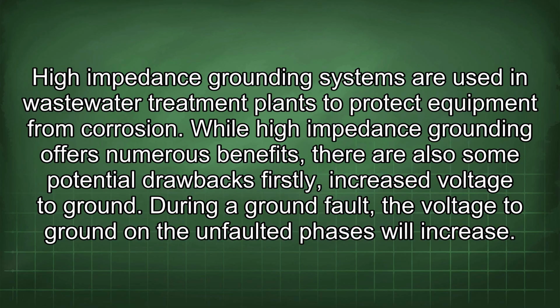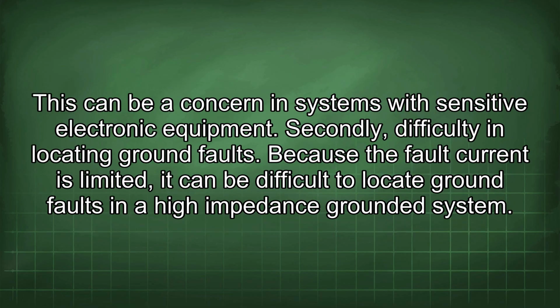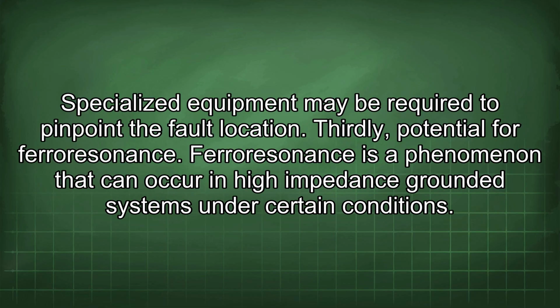While high-impedance grounding offers numerous benefits, there are also some potential drawbacks. Firstly, increased voltage to ground. During a ground fault, the voltage to ground in the unfaulted phases will increase. This can be a concern in systems with sensitive electronic equipment. Secondly, difficulty in locating ground faults. Because the fault current is limited, it can be difficult to locate ground faults in a high-impedance grounded system. Specialized equipment may be required to pinpoint the fault location.